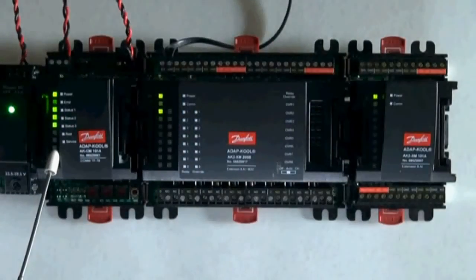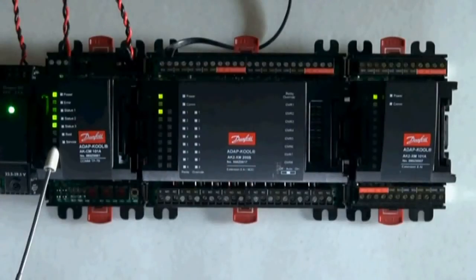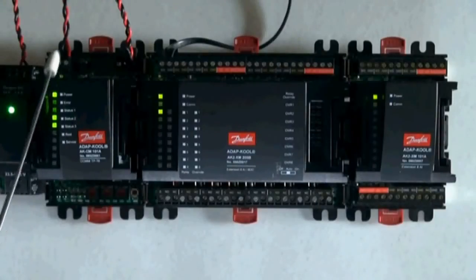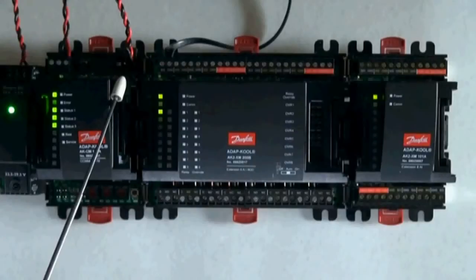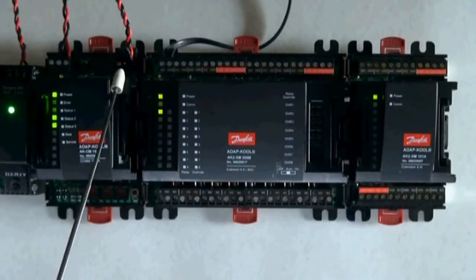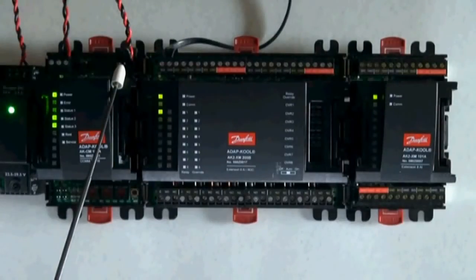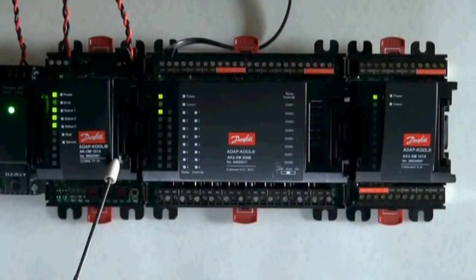Let's take a look at the communication module used to communicate to AK2 modules. At the top we have the power and communication connections. For TP78 communication, such as this, communication modules must be daisy chained. The resistor shown here was removed from the plug inside the AK255 and placed at the last module on the daisy chain. This module can have 9 modules plugged into it. Upon power up, it will recognize the modules installed.